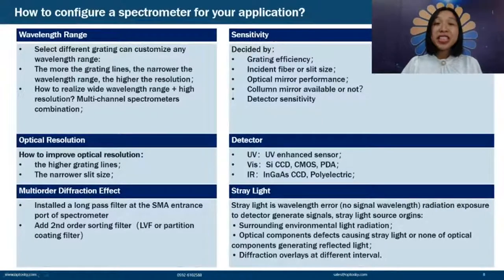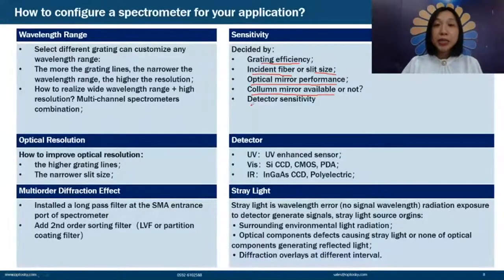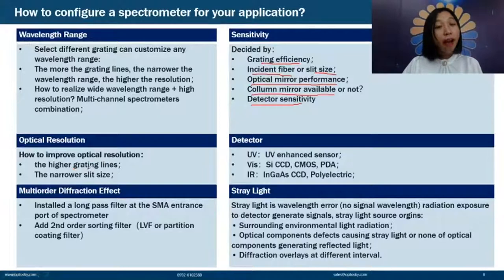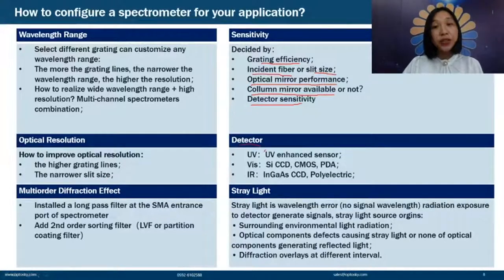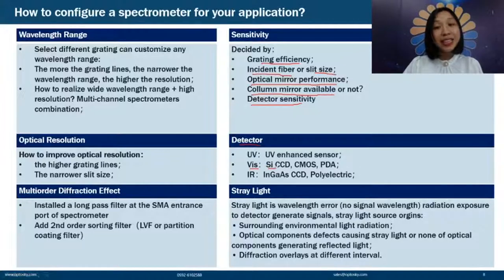Second is sensitivity, which is decided by grating efficiency, incident fiber or slit size, optical mirror performance, whether a cylindrical mirror is available, and detector sensitivity. Third is optical resolution, which can be improved by using higher grating line density, a narrower slit, and by selecting different detectors — such as UV-enhanced sensors for UV range, silicon CCD/CMOS or PDA for visible, and InGaAs CCD or pyroelectric for infrared.